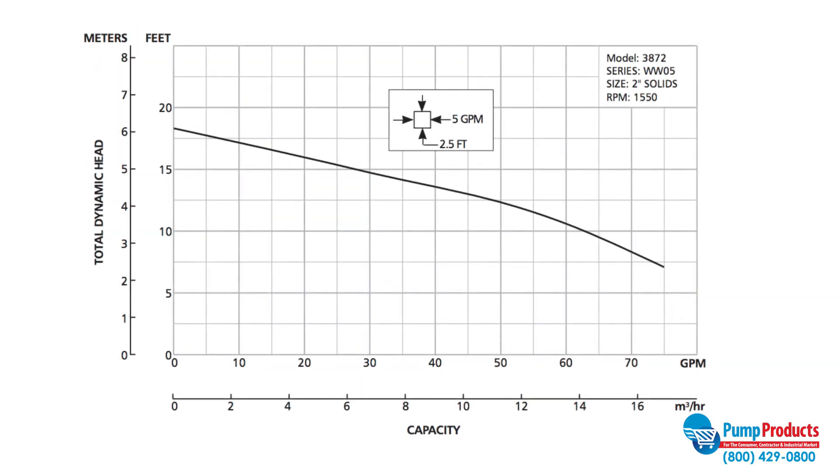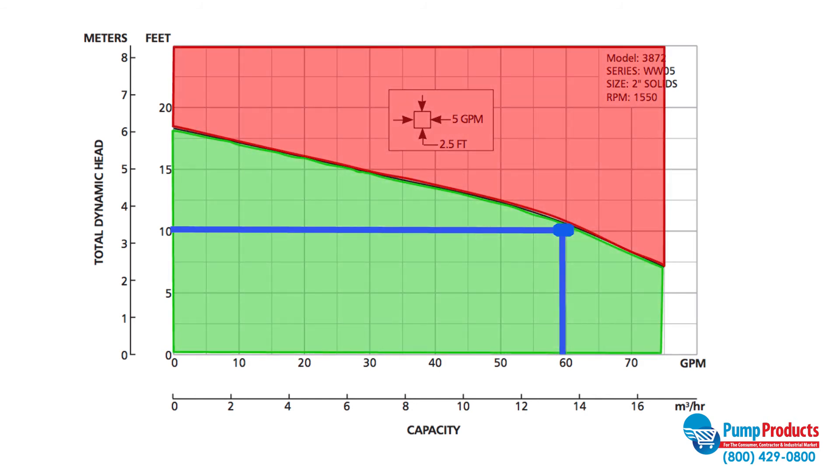Once you know the TDH and GPM your system requires, you can draw a line from each axis and create a point on the chart to represent your system requirements. Ideally, you want your point to fall on the curve as the curve represents the pump's optimal efficiency.